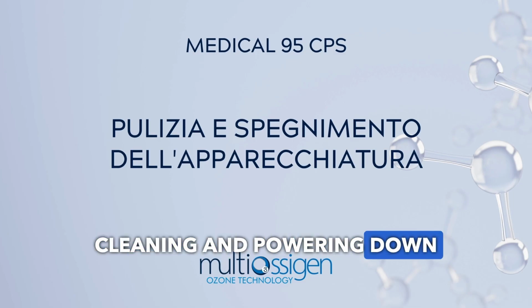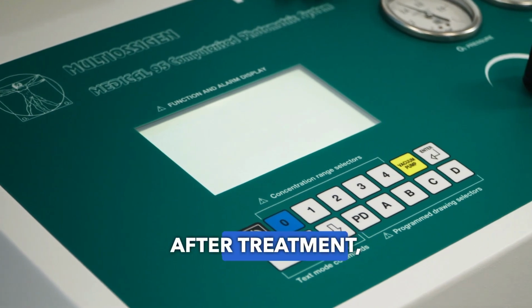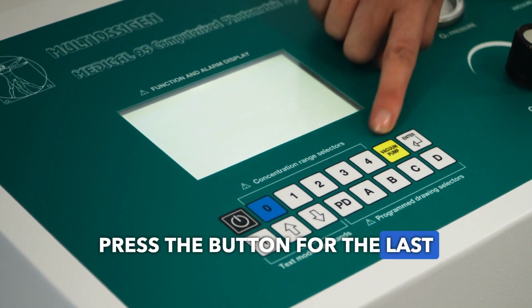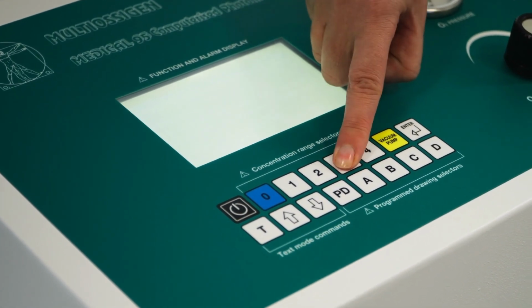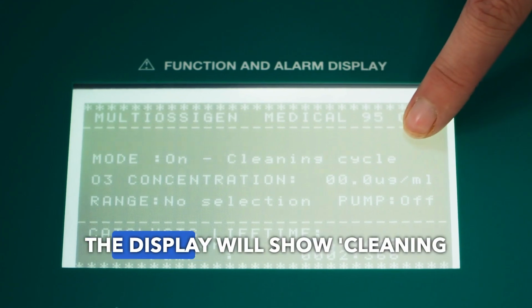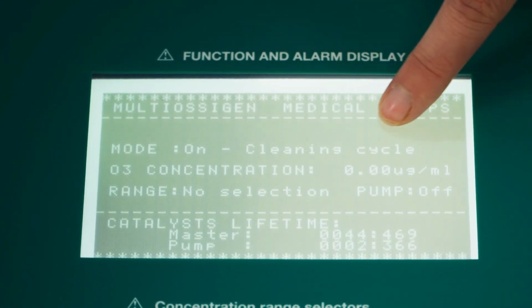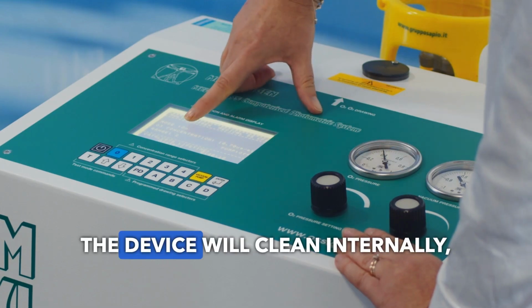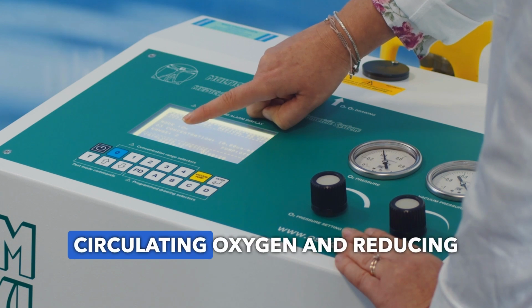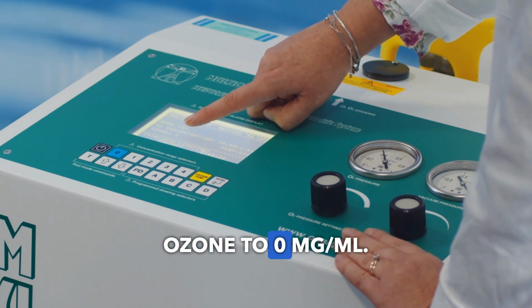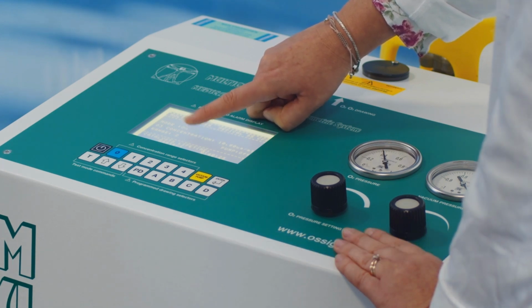Cleaning and powering down the equipment. After treatment, press the button for the last selected range again. The display will show cleaning cycle. The device will clean internally, circulating oxygen and reducing ozone to 0 micrograms per milliliter.